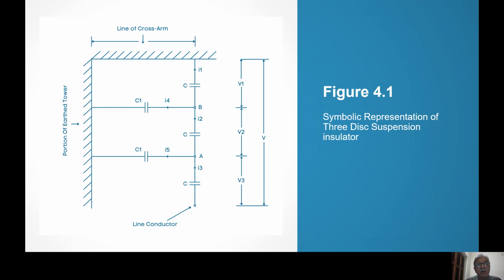So C1 is the same, but I5 will reduce, and that is the advantage. But if you use a very long cross arm, it becomes very costly, and there are many towers in the line, for a 100-kilometer long line, usually 3 towers per kilometer. So the line becomes costly, and that solution is not much feasible.